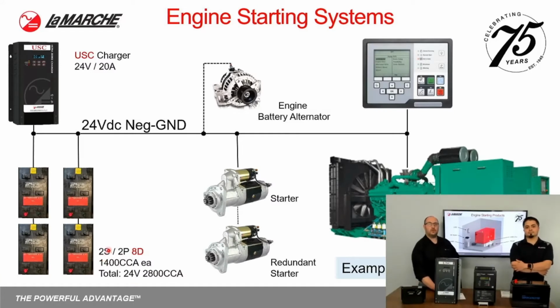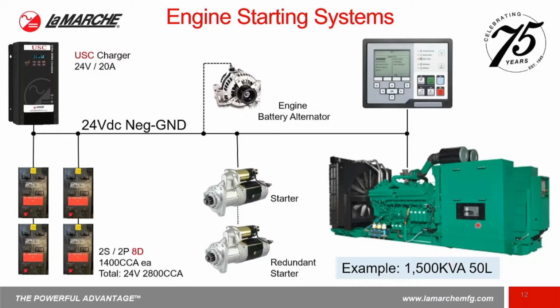So let's look at the total DC system. Starting with a USC battery charger. What would be typical in this class would be 2 series, 2 parallel 8D batteries. Each one of these are 1400 cold cranking amps. When you wire them in series, the cold cranking amp stays the same, but the voltage grows to 24 volts. But being that there's 2 in parallel, now we have a 24 volt system that's capable of 2800 cold cranking amps. Like I said, that'd be typical for a generator approximately this size.